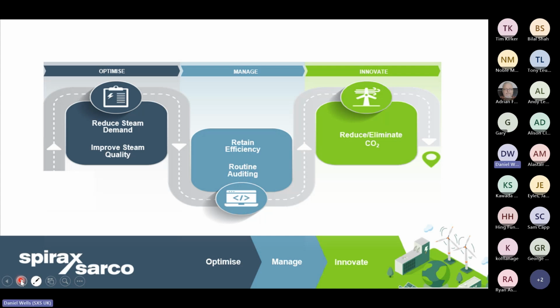For example, the three-step approach that you can see on the screen really emphasizes the fact that the vast majority of those traditional steam systems that were engineered 25, 30 years ago are going to have a significant number of inefficiencies. So the first thing we need to do is really understand how efficiently or how inefficiently our client's steam system is operating. And from then on, we can understand the significant benefit we can bring to our client by addressing those immediate inefficiencies.